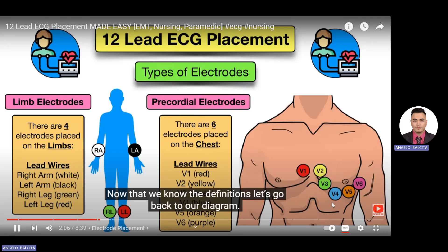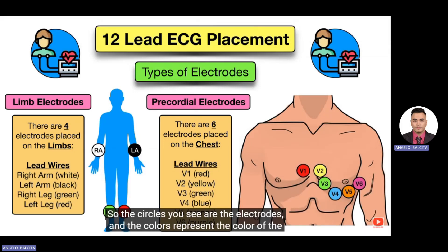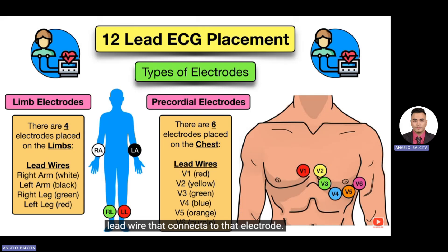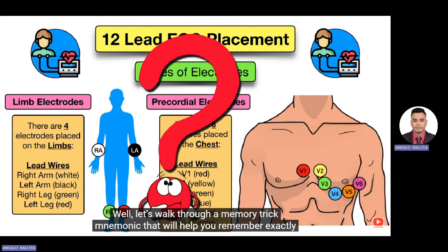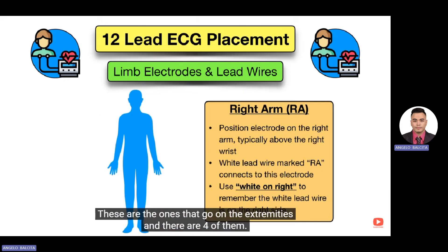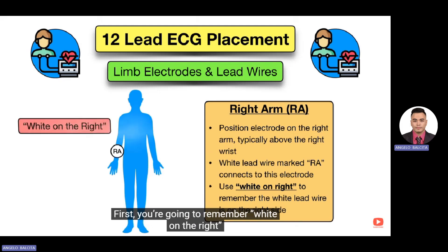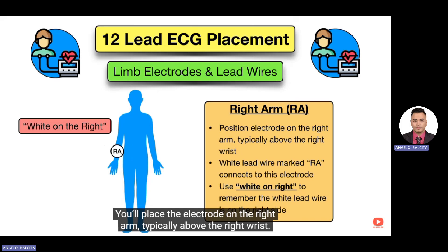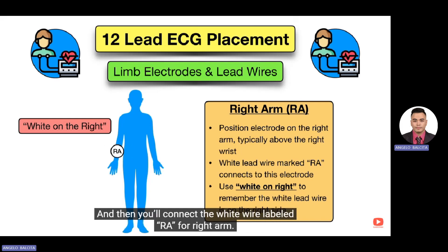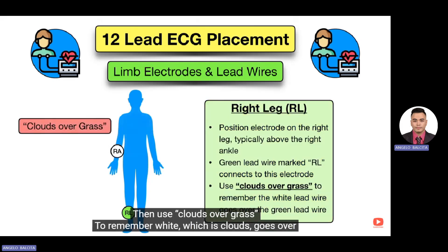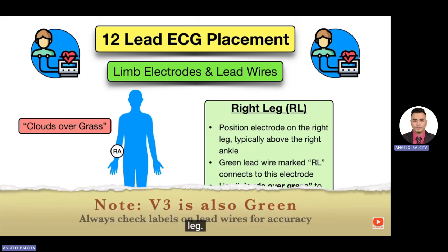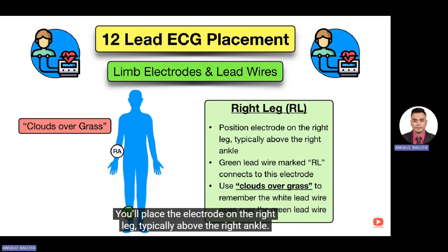Now that we know the definitions, let's look at limb electrode placement. First, remember 'white on the right' — the white lead wire goes on the right arm, placed typically above the right wrist, and connected to the wire labeled RA. Next, use 'clouds over grass' — white (clouds) goes over green (grass). Since white is the right arm, green is the right leg, placed above the right ankle and connected to the wire labeled RL.